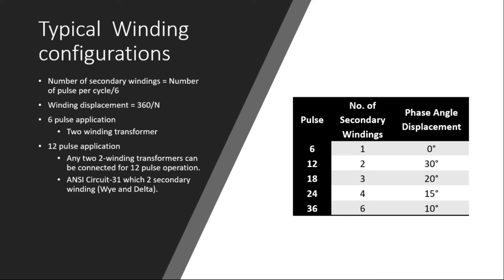The winding displacement you need between the secondaries you can calculate by 360 by n. For example, in this 12 pulse application, you need 30-degree displacement between two secondary windings. For 12 pulse, we saw the most commonly used industrial configuration is ANSI circuit 31, where you have 2 secondary windings, one Y and one delta. Since we know the difference between the Y and delta line voltage is 30 degrees, that will be used to get this 12 pulse requirement.